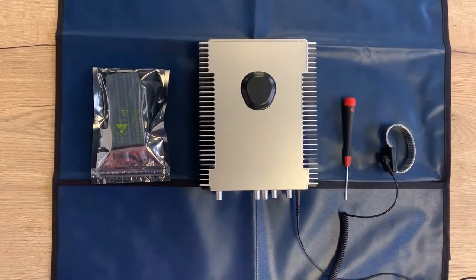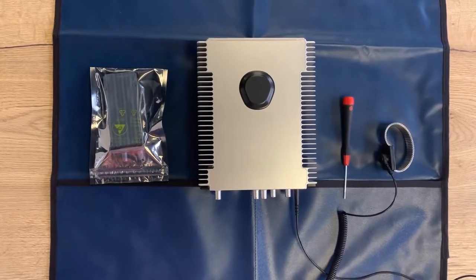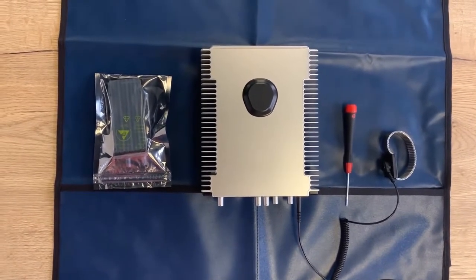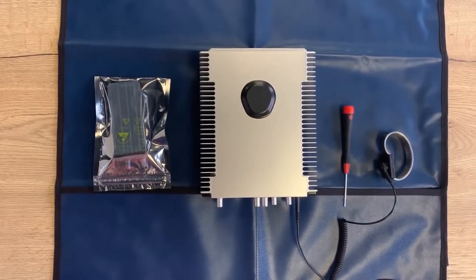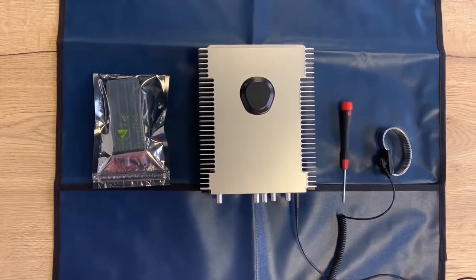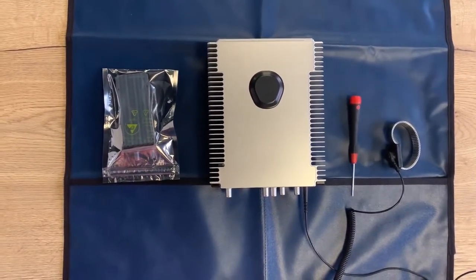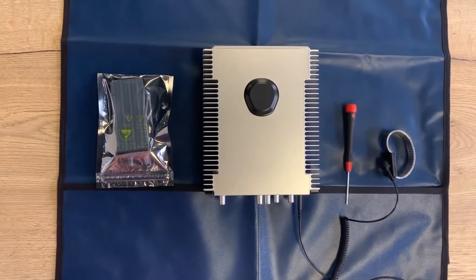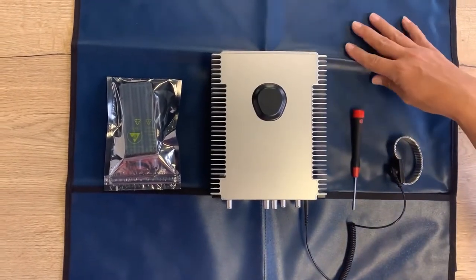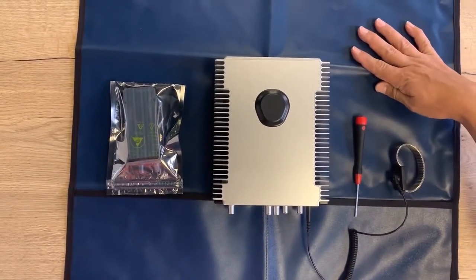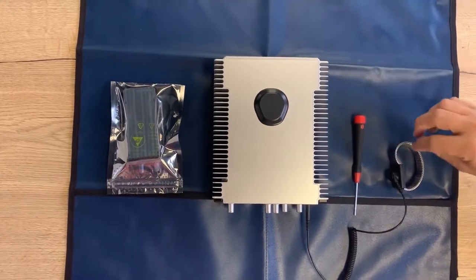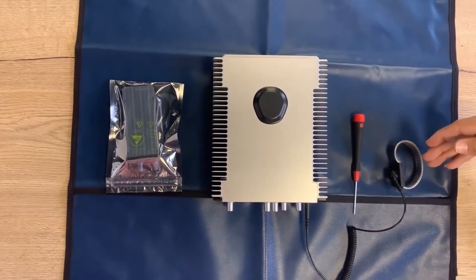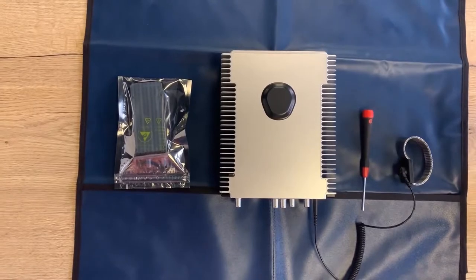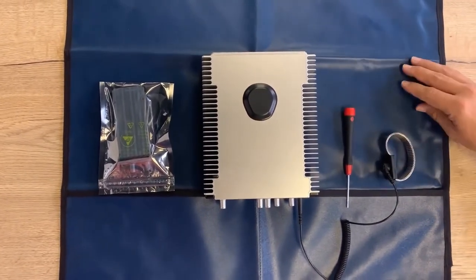We'd like to take a few moments to talk about the proper way to handle hardware for your MICROQ when you're exchanging a module. So there are a few elements that we need to take care of to make sure the system is not damaged from ESD. The first thing we have is an ESD mat because we're not in an ESD safe environment, and that includes the wrist strap, and that will make sure that I'm at the same potential as the MICROQ.